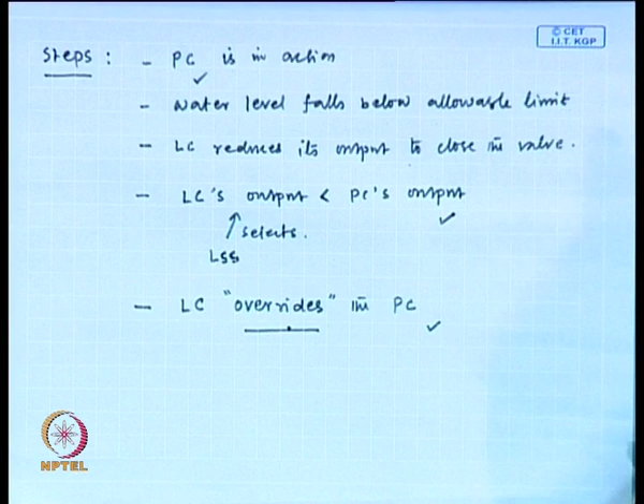So, we can say that the level controller overrides the pressure controller. Fine. Therefore, this controller is also called an override controller. Previously, we discussed the reason to call it a constraint controller, and this is the reason to call it an override controller. So, in this example, we have discussed the application of LSS. LSS selects basically the lower output signal. For the case of HSS, the fact is opposite. HSS selects the higher output signal. Fine. So, this is about the constraint controller.